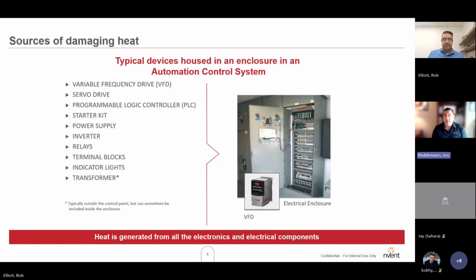A great example is a solid state relay versus the old cube relays. The old cube relays that everyone's used to didn't really produce any heat, but a solid state relay, if you're replacing from a cube to an SSR, will produce between 1 to 1.5 watts per amp going through the relay. So if you had a 30 amp cube relay, it didn't produce any heat, but we now have a 30 amp SSR, we've now got between 30 to 45 watts of heat.